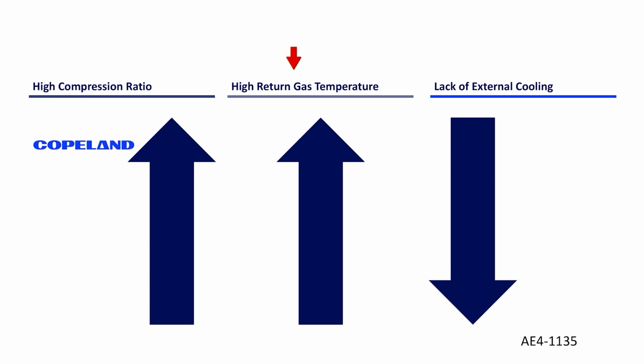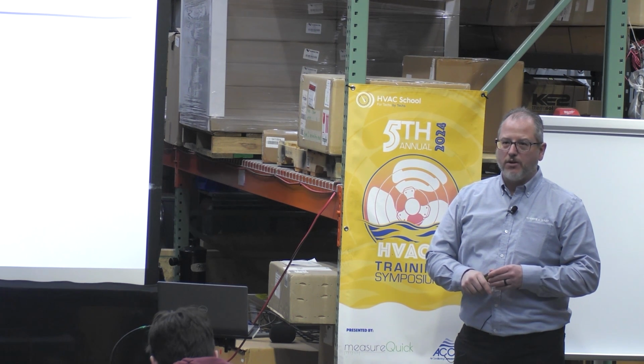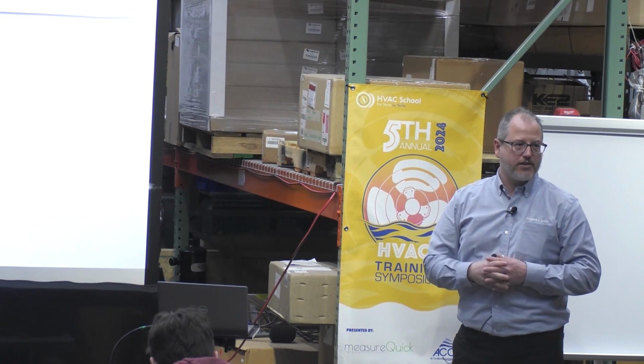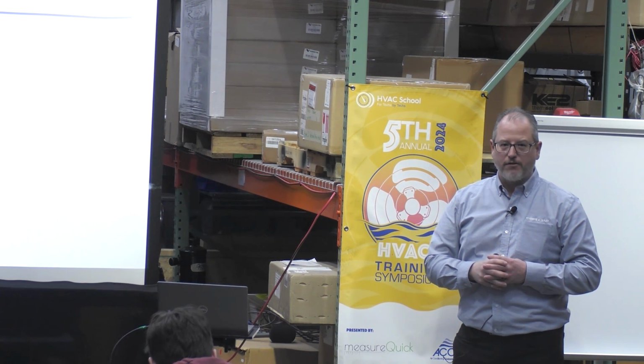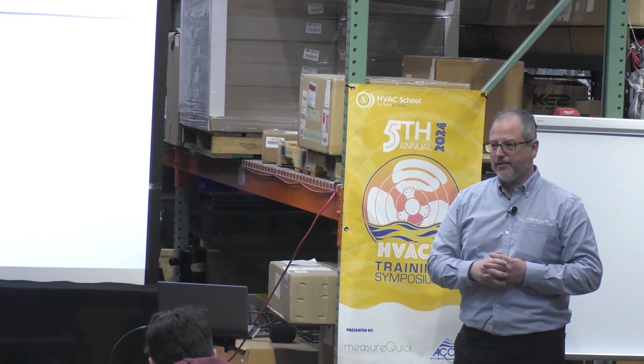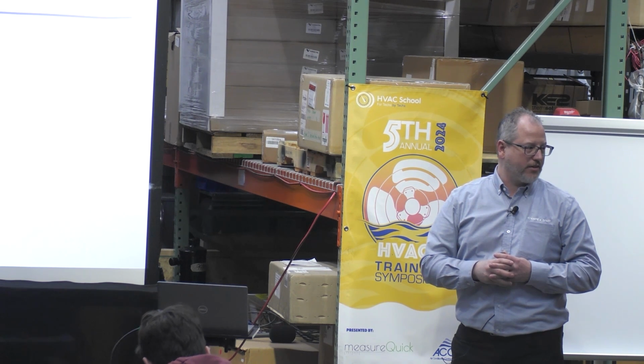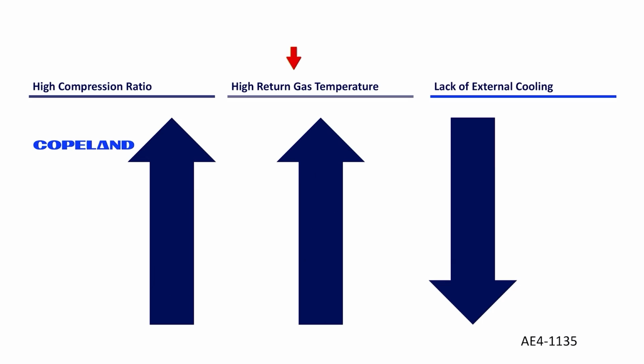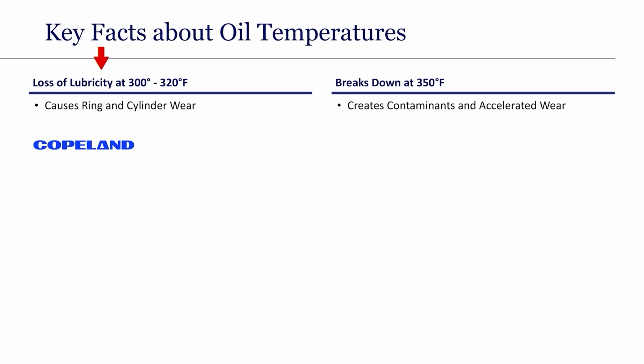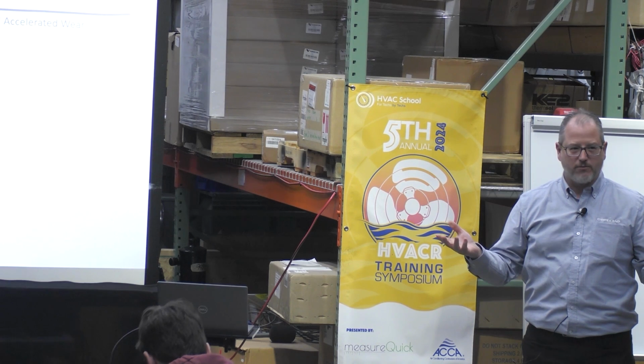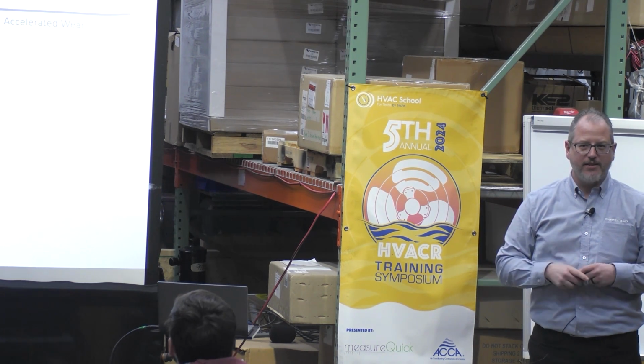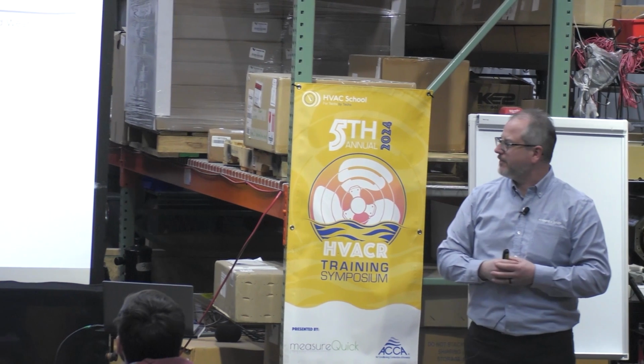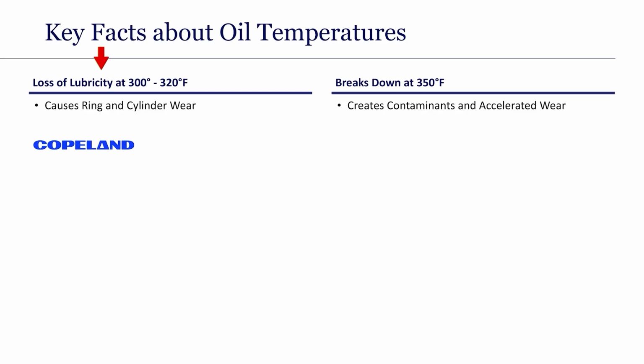High return gas temperatures. Say we have a unit on the roof, and we're in Phoenix, Arizona. We have a nice black roof and no insulation on that suction line. What do you think is going to happen to that suction line? Do you think it's going to gain a little bit of heat? Absolutely it is, so that heat is going to affect that system. Once we get to about 300, 320, our oil starts to lose lubricity. Now that's just a fun word to say, so I like to put that in all my trainings: lubricity. Say that at home. 300 to 320 degrees.